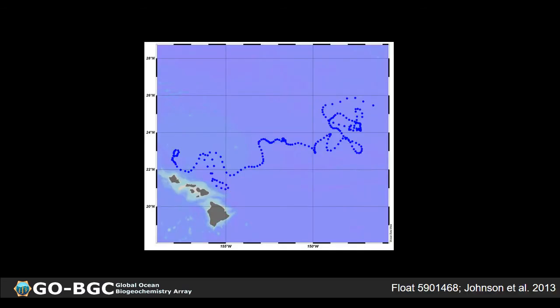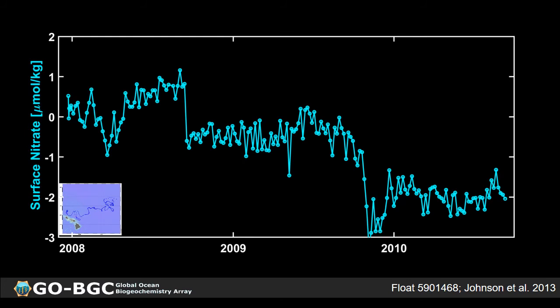To demonstrate how nitrate sensors drift, I'm going to show you some data from a profiling float that was deployed off of Hawaii. This is a good float to use because we know from the Hawaii Ocean Time Series data that the surface nitrate is always zero no matter the time of year. So that provides a really convenient reference measurement that we can use to assess sensor drift. This is a time series of the float surface nitrate over the course of about 3 years. You can see that it started off around 0, but then over several years, the surface nitrate decreased to about -2, which indicates that the sensor is drifting low by several micromoles per kilogram.